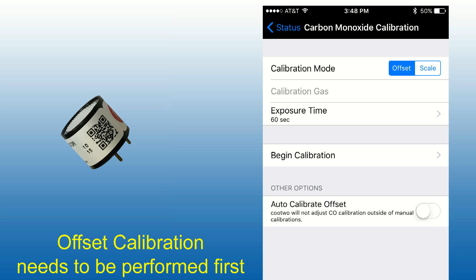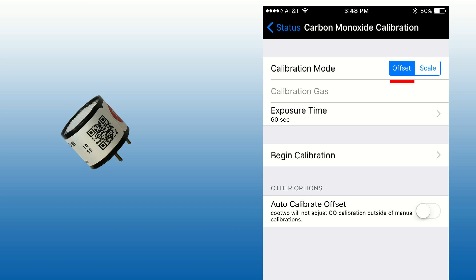The offset calibration must be done first. To perform the carbon monoxide sensor offset calibration, select Offset. Then select the exposure time — minimum of 60 seconds.